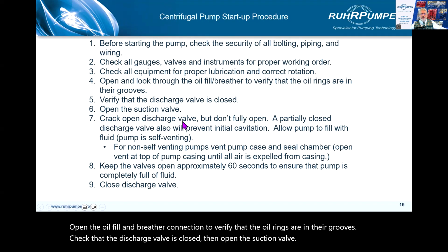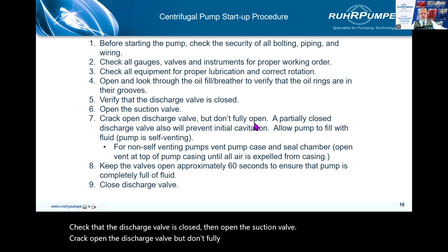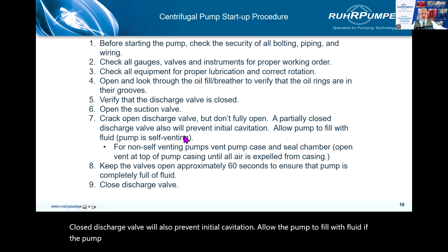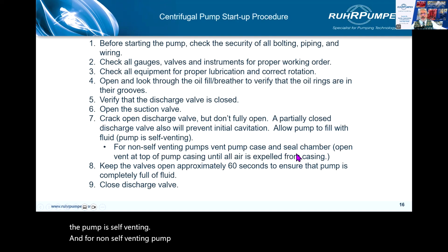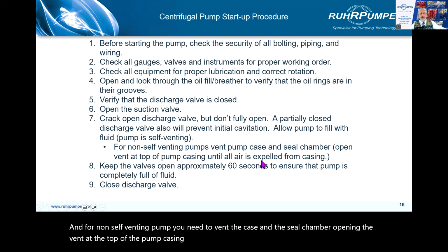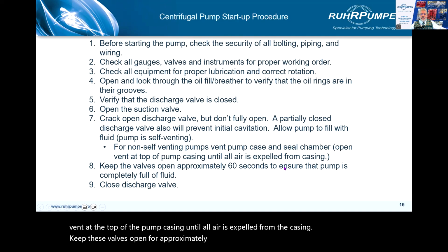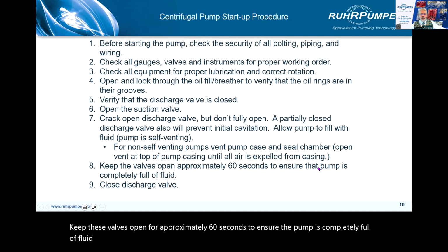Crack open the discharge valve, but don't fully open. A partially closed discharge valve will also prevent initial cavitation. Allow the pump to fill with fluid if the pump is self-venting. And for a non-self-venting pump, you need to vent the case and the seal chamber, opening the vent at the top of the pump casing until all air is expelled from the casing. Keep these valves open for approximately 60 seconds to ensure the pump is completely full of fluid, then close the discharge valve.